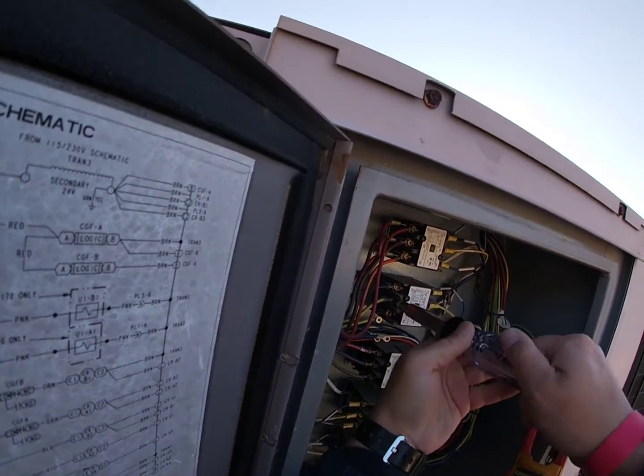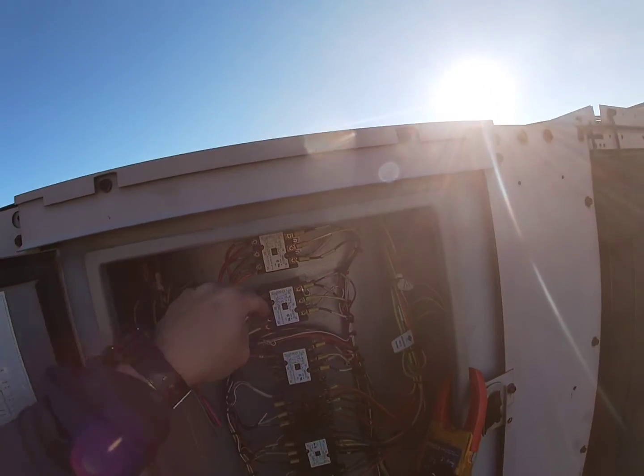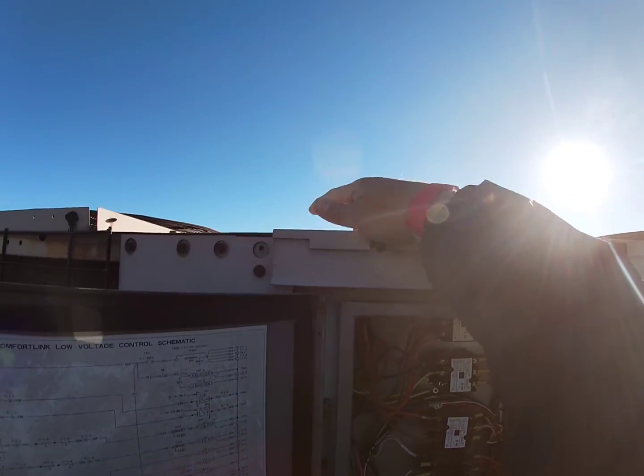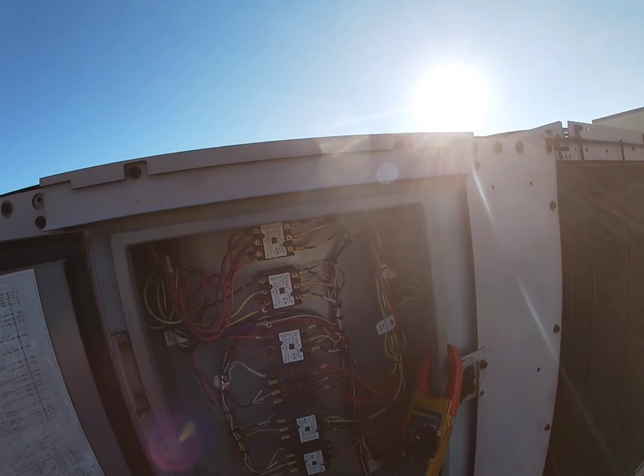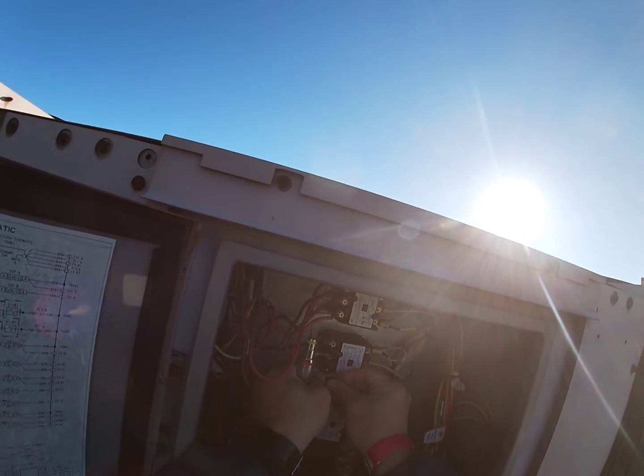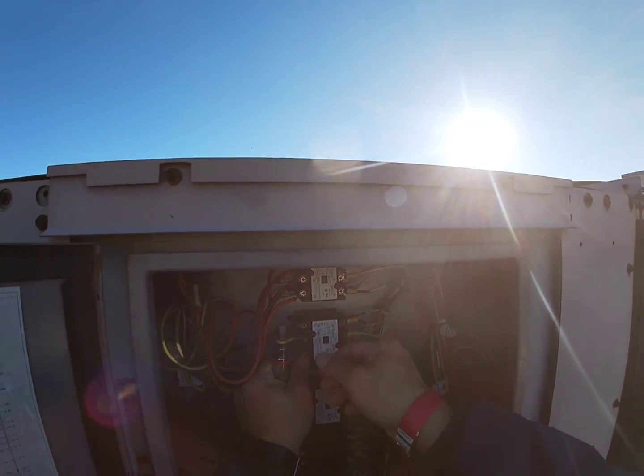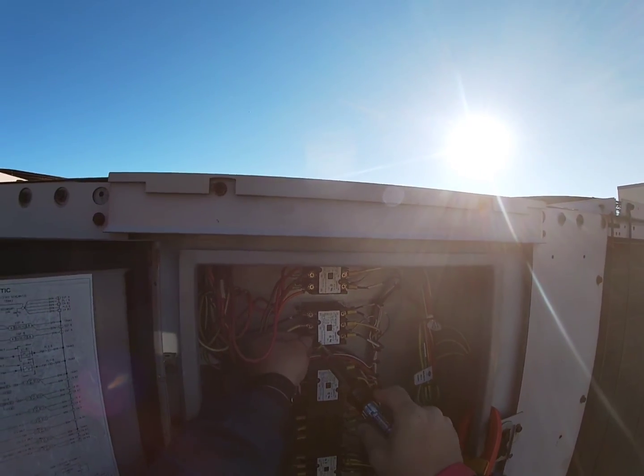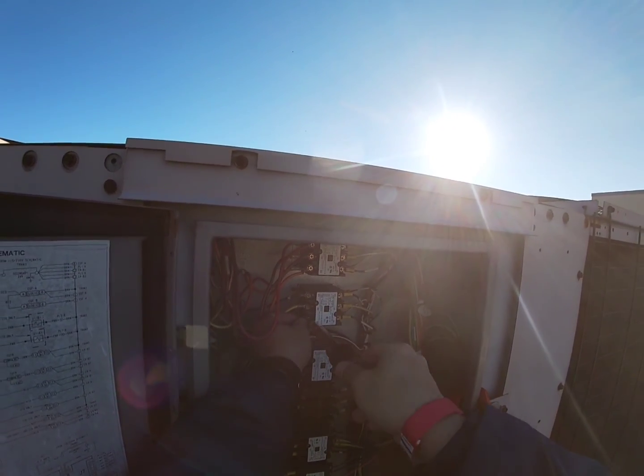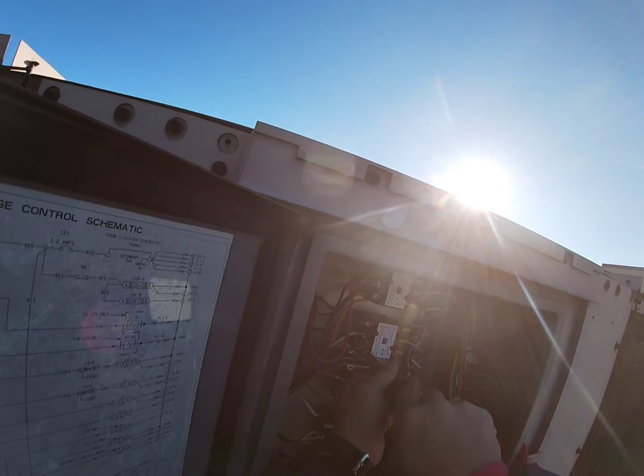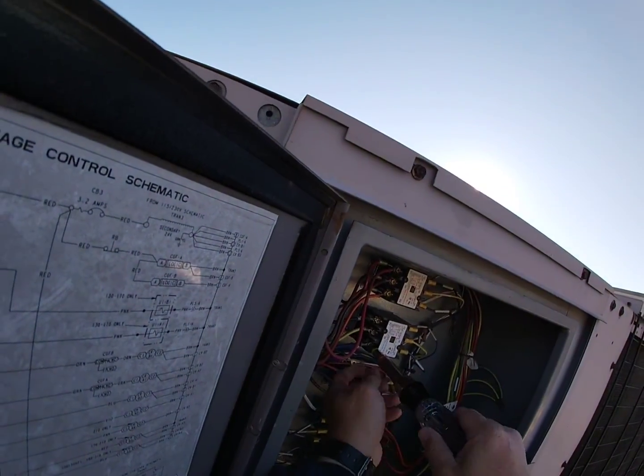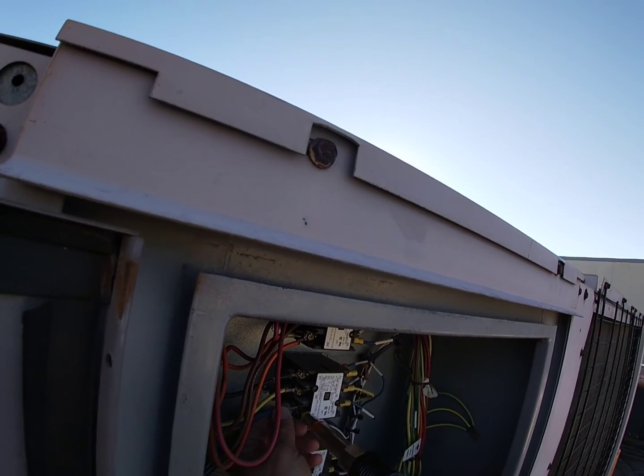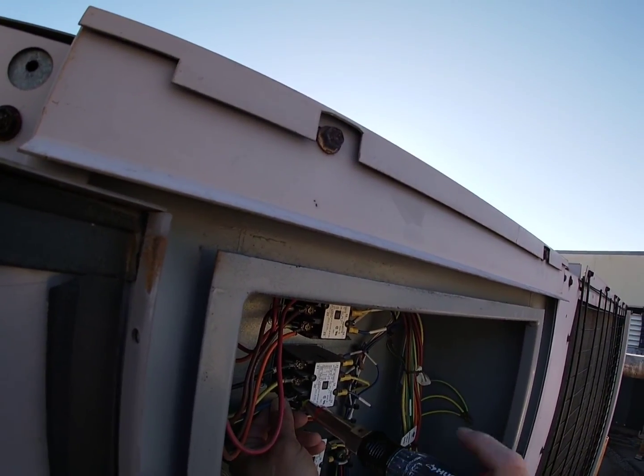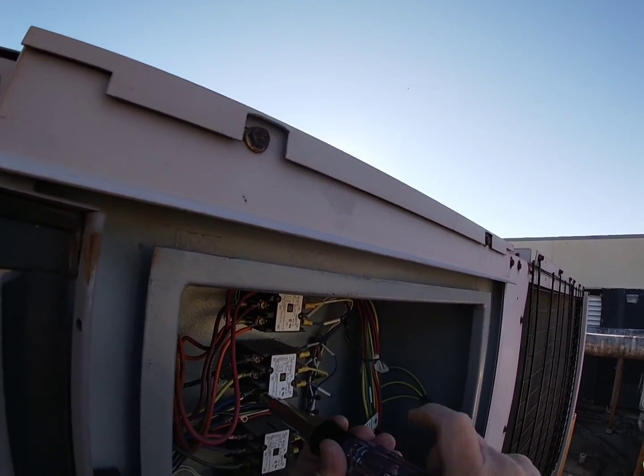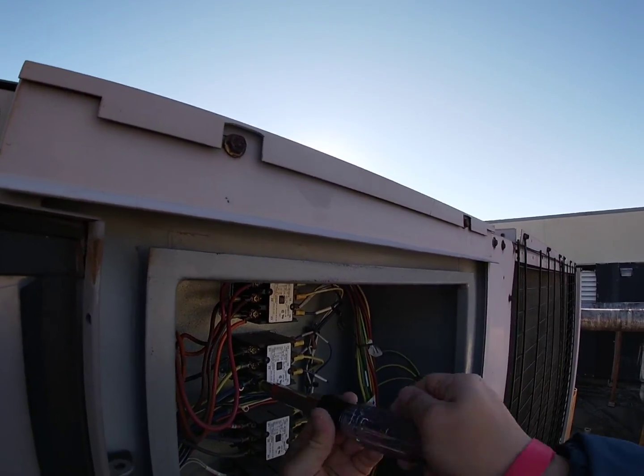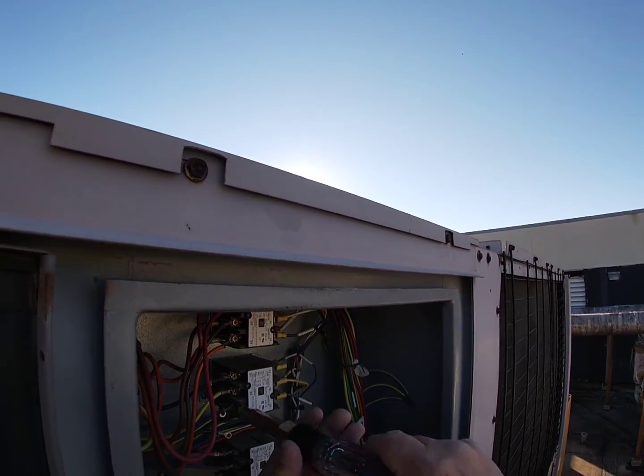So obviously we don't want to reset anything without checking everything first, because if you do, you don't want this thing to blow in your face. You don't know what caused that breaker to trip. So one very important thing to do is before just resetting the breaker, you want to go ahead and double check everything before just hitting that reset. I've seen it before, and I don't want it to happen to me.